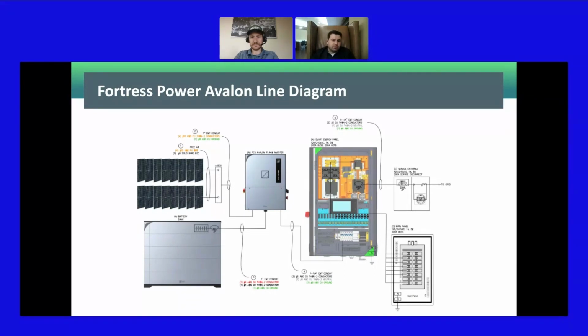So the key thing to remember is 18 kilowatts of DC coupled solar connects to the inverter, and AC coupled solar connects to the smart energy panel, but the limit on it will be 12 kilowatts because the AC coupled solar has its own load shedding ports, which are capped at 50 amps.